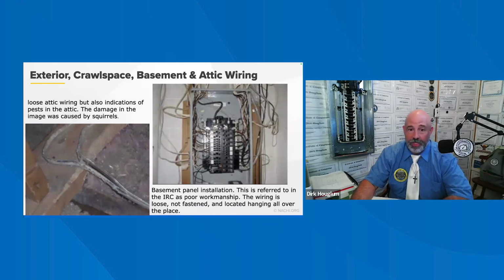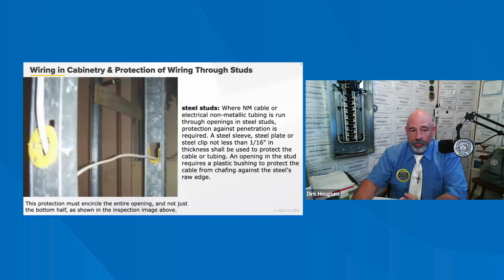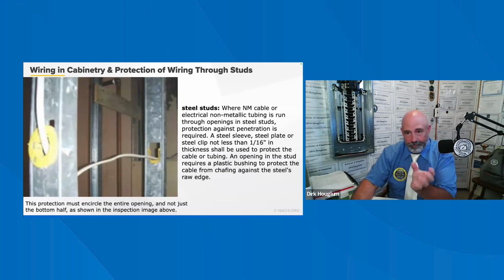That is a hazard. I see loose wiring a lot of times in crawl spaces. You should have that attached properly, and it's really important that people understand that this is safety. You don't want a kid crawling underneath there and pulling on some wires and causing your TV show to go off, right? Come on. Steel studs, make sure that they have the proper insulating brackets.